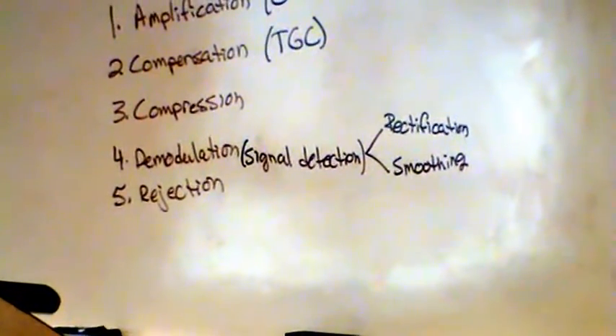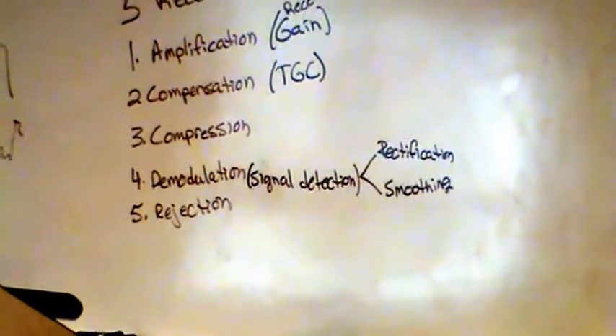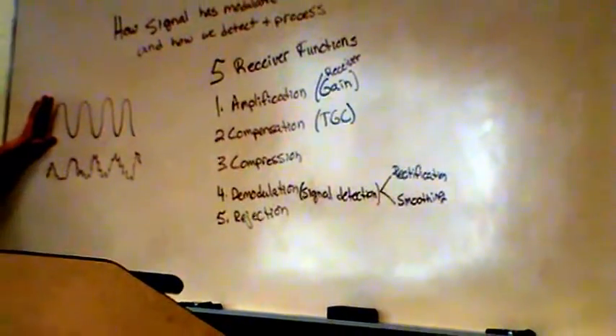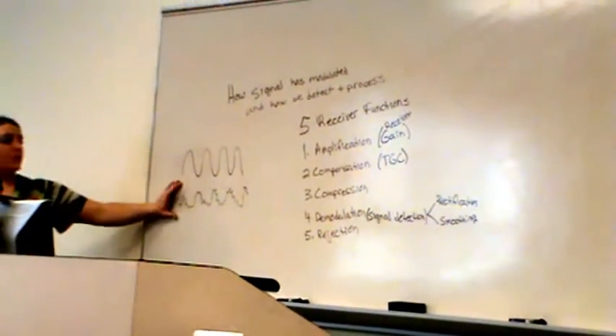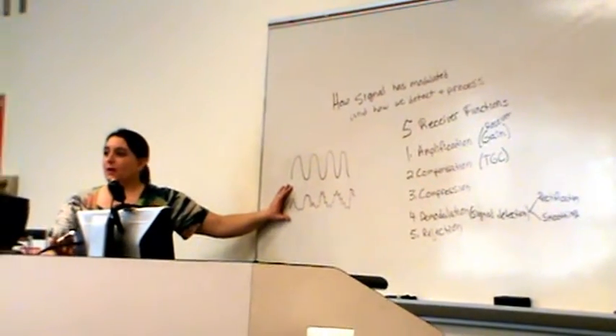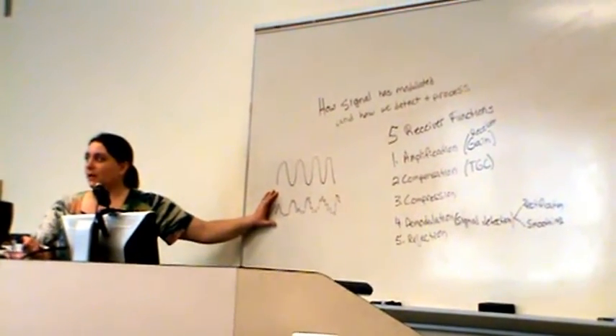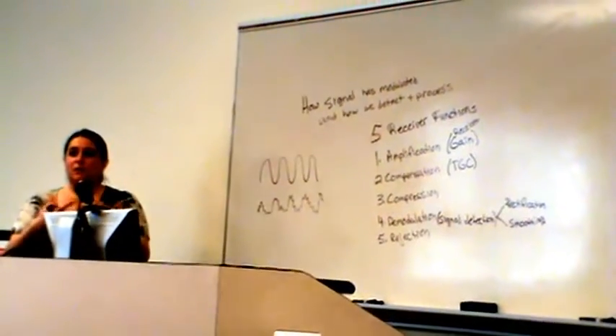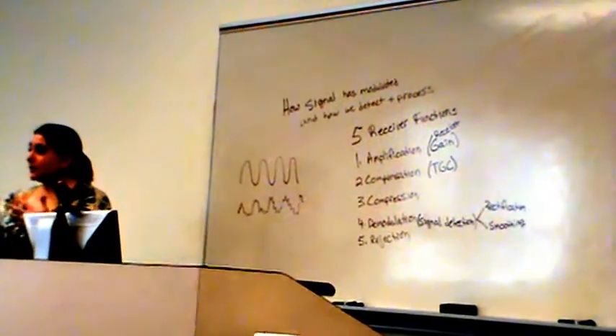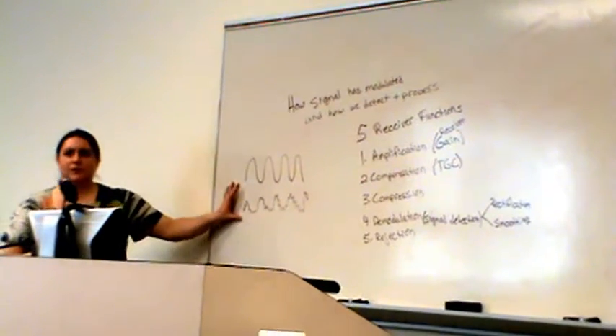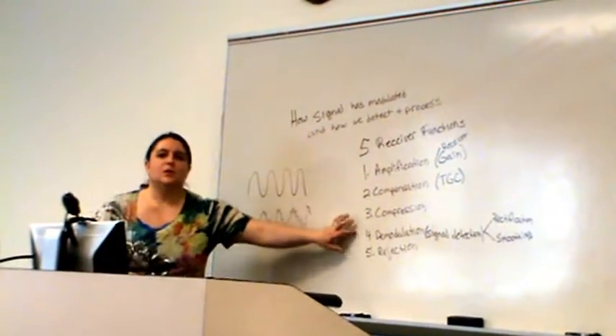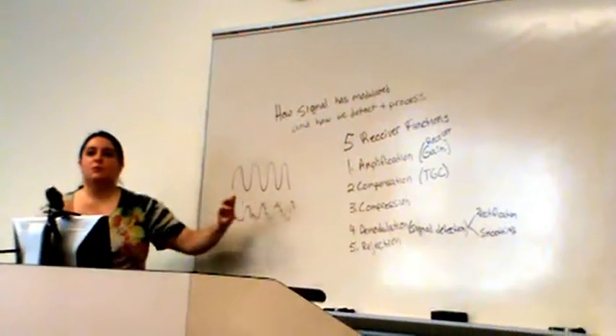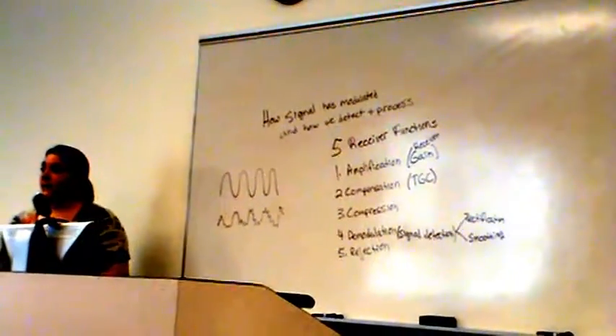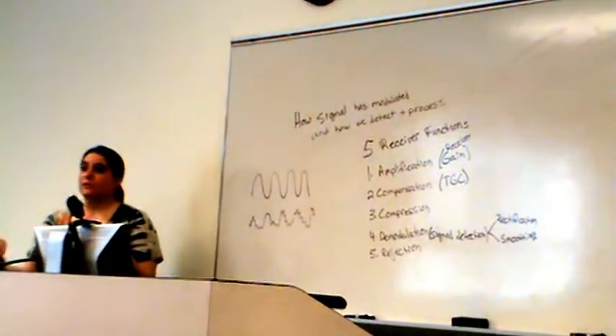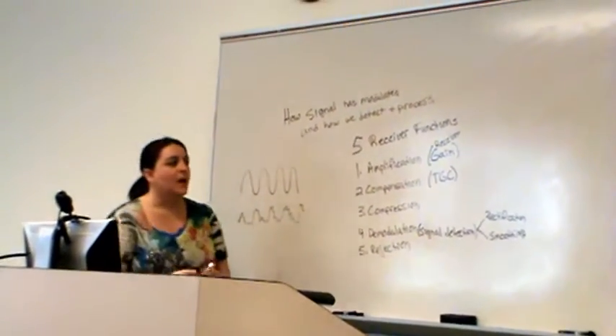So in this step, this is the step that's really going to separate out what we sent in from what we got out. So we sent in this raw signal, and say we sent in something that was 2 megahertz. We know we sent in a 2 megahertz beam with that frequency, and we know what amplitude we sent in. So then what came back out was roughly 2 megahertz, but it has all these weird frequency changes in it. There's kind of this weird mixing. We talked about the mixer in relation to Doppler signal detection. There's also kind of a mixer in imaging signal detection in this demodulation step that mixes this signal in with the signal that we know we sent in and separates them out. So we kind of subtract out the 2 megahertz beam that we know we sent in.